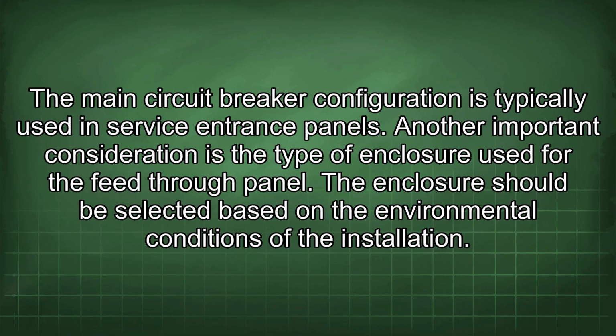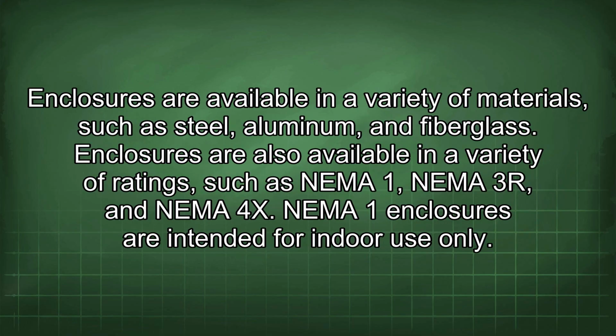Another important consideration is the type of enclosure used for the feed-through panel. The enclosure should be selected based on the environmental conditions of the installation. Enclosures are available in a variety of materials such as steel, aluminum, and fiberglass. Enclosures are also available in a variety of ratings such as NEMA 1, NEMA 3R, and NEMA 4X.